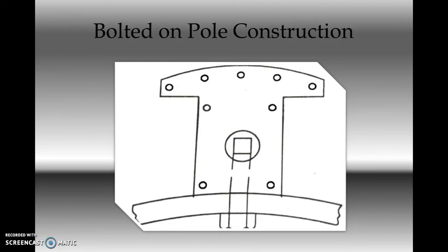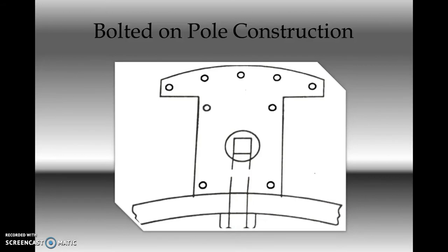This is a diagram for bolted-on pole type of construction. The projected pole is fixed on the outer rim of the rotor yoke. Here we can see that it is the rotor outer periphery and this projected pole is directly riveted or bolted on the outer periphery. It is one of the simplest types of construction, known as bolted-on pole type, used for 20 to 25 meters per second peripheral speed.